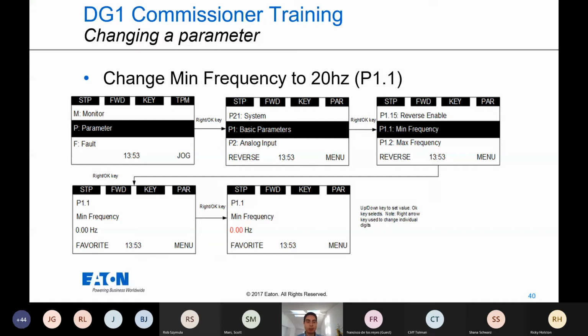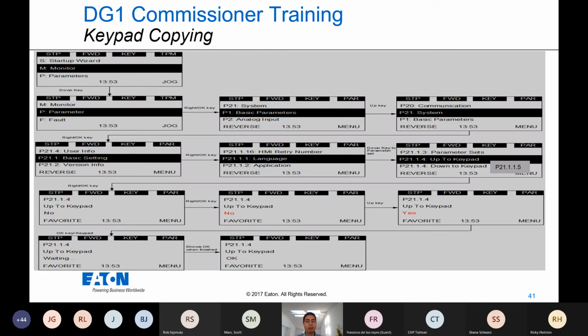It is a simple way to update and change this on your VFD. Here are some examples of how you would do it if you were to go on the parameters with the drive. And then again, be able to upload the data from your VFD to have as backup to use for, let's say, an emergency or secondary storage keypad. You can use that simply. It's a little bit more complex, you have to go through more steps, but you can also do this by connecting your computer directly onto the VFD.